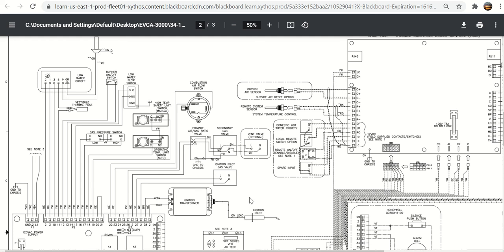If you remember from the traditional flame safeguard, these are the three outputs that it controls. It tells the ignition transformer to provide a spark, opens the pilot solenoid valve, proves that the pilot gas or pilot burner has lit. There's pilot flame there, and then it shuts the ignition transformer off, and the pilot flame lights the main flame, and then the pilot shuts off. That's typical for the sequence of an RM7896.